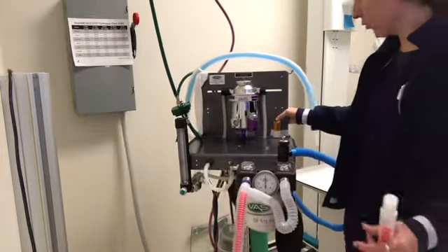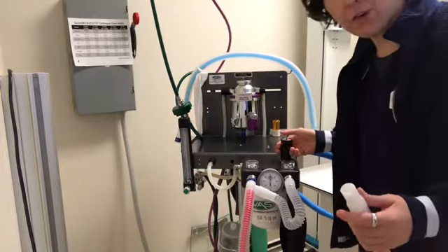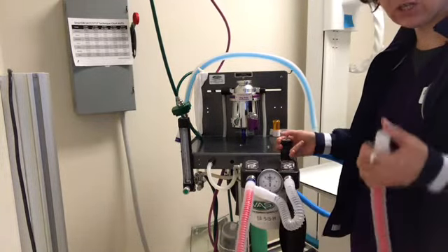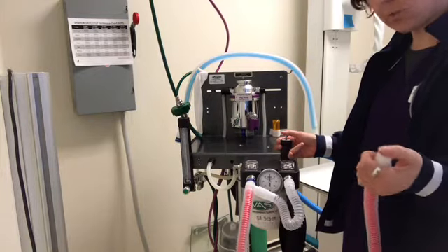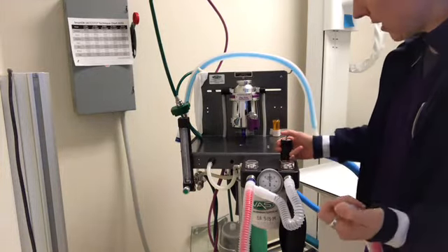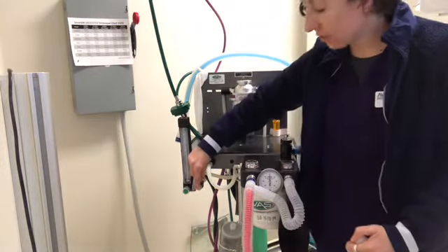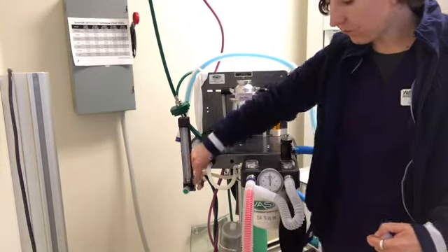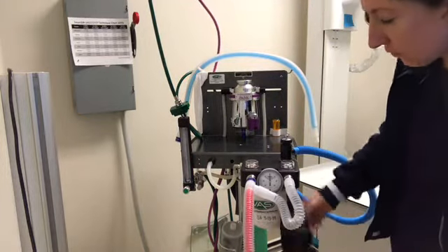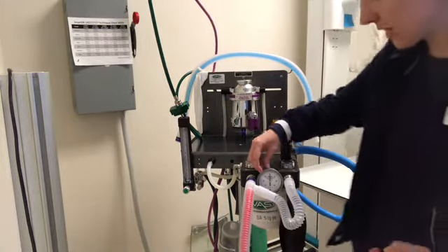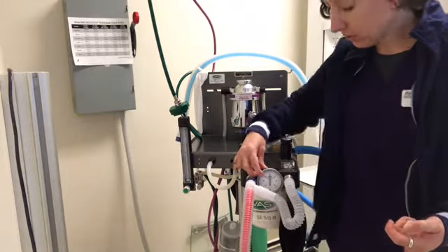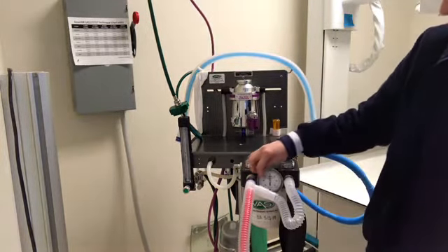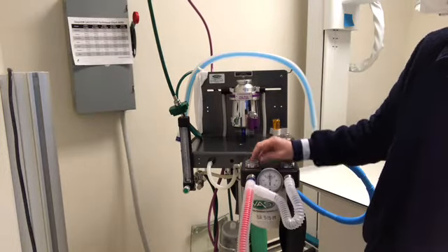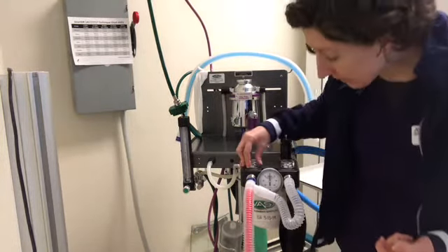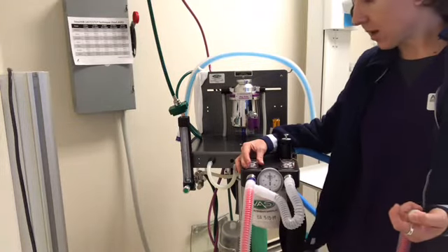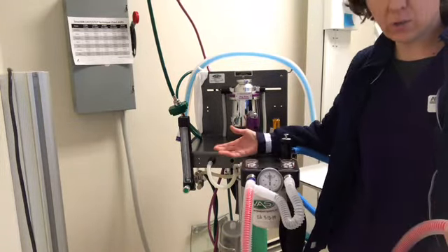So what I'm going to do is close my pop-off valve right here with my right hand. I'm going to occlude the tubing with my left hand, and I'm going to press the oxygen flush valve until my bag fills up and the manometer reads about 20 centimeters of water. And I'm going to watch to make sure that that needle does not drop more than 1 centimeter per second. If it drops faster than that, that means we have a leak.